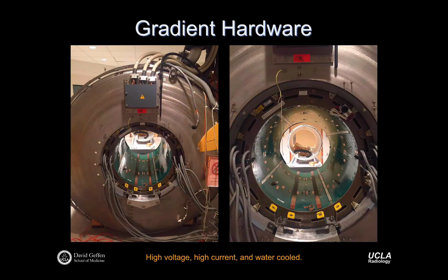We talked about it a little bit before. You can see these slots, these trays here. Those are the trays that you could slide in and out to help make your B0 field more homogeneous. So if you turn off the field, you can pull out those trays. You have to turn off the field because they're full of these ferromagnetic cards, right? And then you can redeck it. You can put in different cards, slot it back in, ramp up your field, measure it, see that it's within specification.